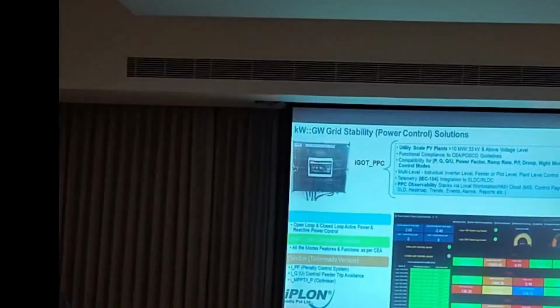Starting with grid stability for utility scale PV plants: in India, we have CEA guidelines for project sizes above 10 megawatts. Whenever the point of interconnection is above 33 kV voltage level, we must have a closed loop power control solution installed in the power plant for the first time grid interconnection.